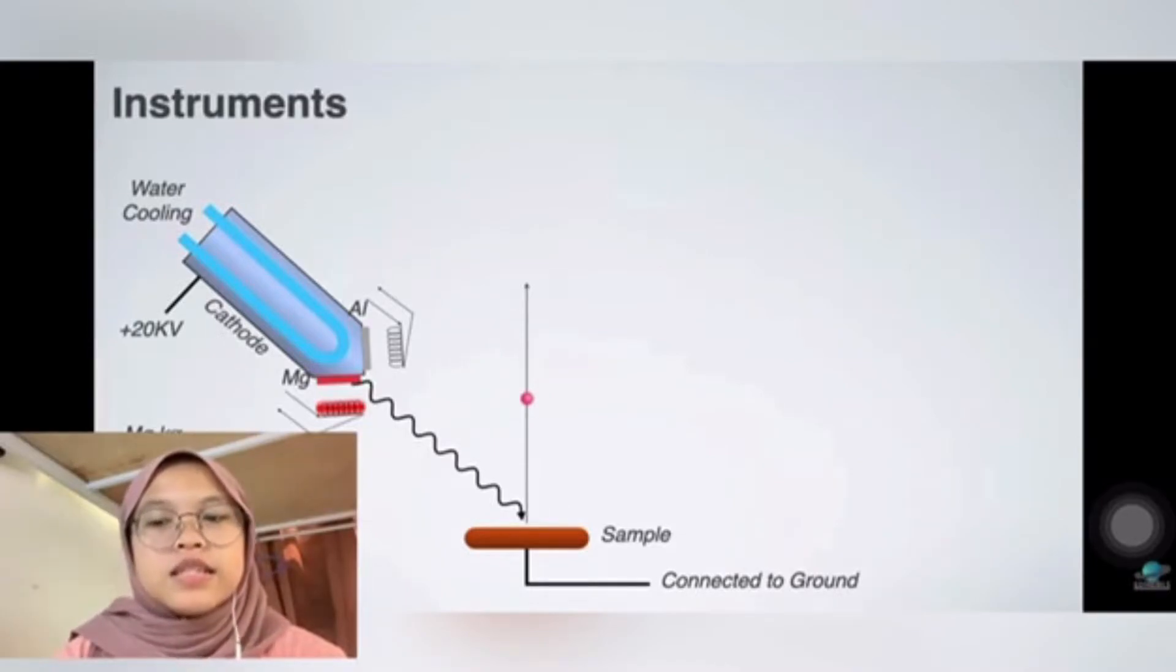Moving to the next one is the lenses. Lenses collect the emitted electrons which are focused on the entrance of the analyzer lens and slit system.